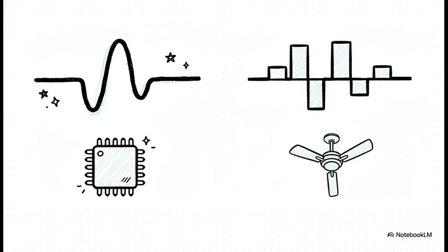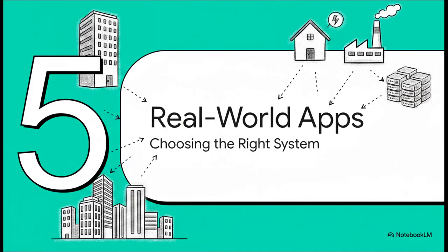An IPS, however, often produces a modified or square sine wave. It's blocky, it's stepped, and it's harsh. It's totally fine for spinning a ceiling fan, but it will cause sensitive IT equipment to run hot, buzz, or completely fail over time.